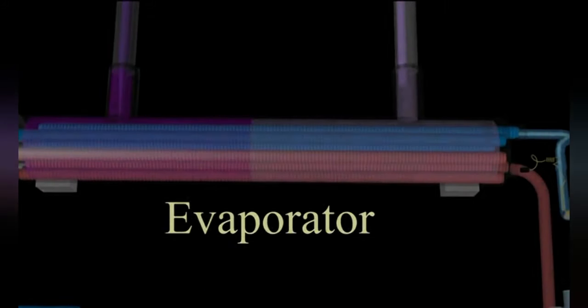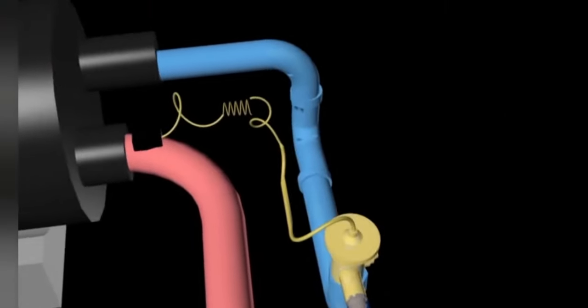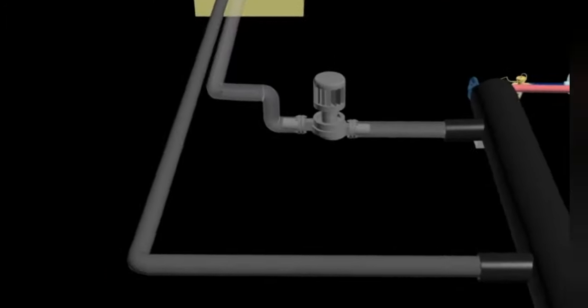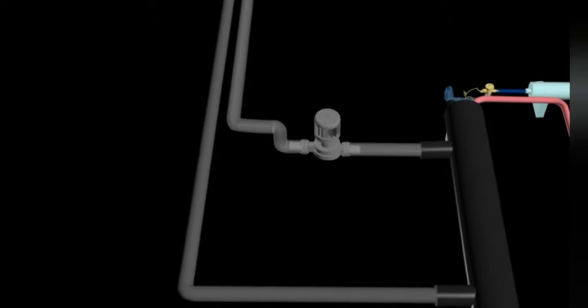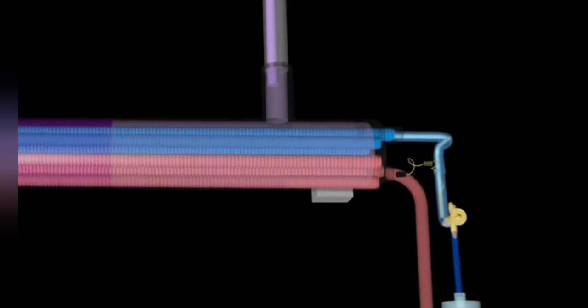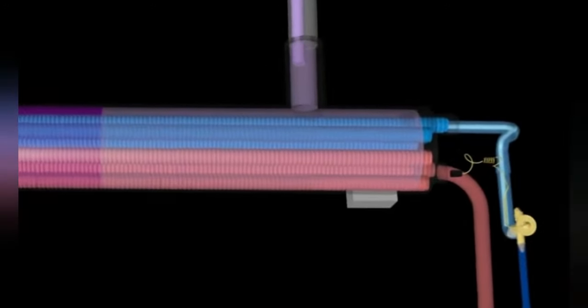The refrigerant in low pressure liquid form coming out from the expansion valve flows into the evaporator at low temperature. In the evaporator, heat from the chilled water returning from the air handling unit is absorbed by the refrigerant due to the temperature difference. When the low temperature, low pressure liquid refrigerant absorbs heat from the chilled water, it evaporates into low pressure gas.